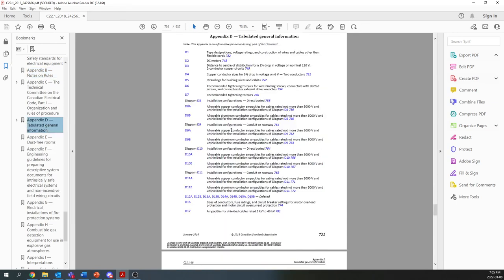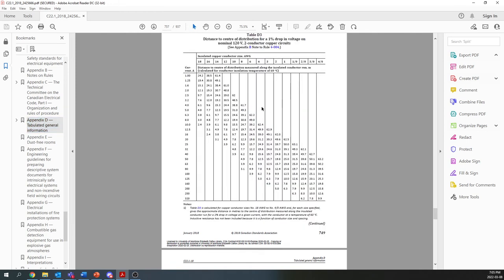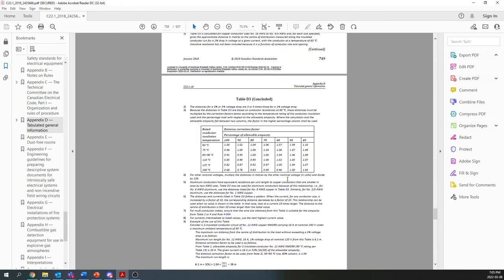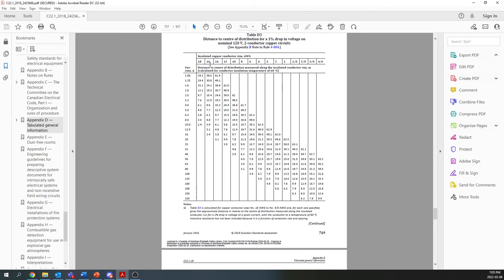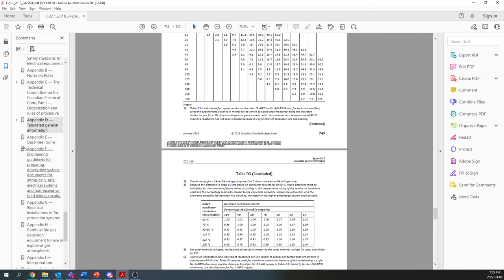Appendix D, tabulated general information, is also very important and very useful. There's a number of tables in here that are used all the time. Tables D8A to D11B are used for finding the ampacities of large feeder cables and conductors that are installed underground. For example, table D3 here is a table for calculating voltage drop. This is kind of like a standardized table with some distance correction factors that you can use for various currents and sizes of wiring, and you can see how long you can go for X voltage drop. In this case it's 1%, but then you can multiply this to get 2, 3, 4%, whatever you need.